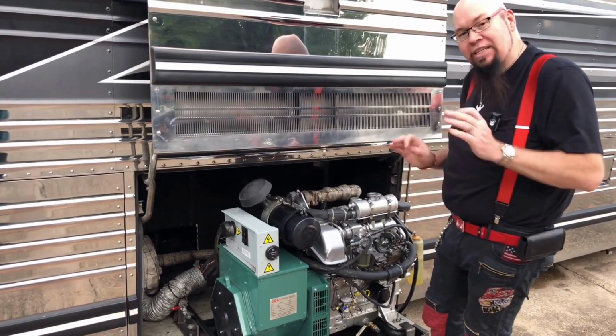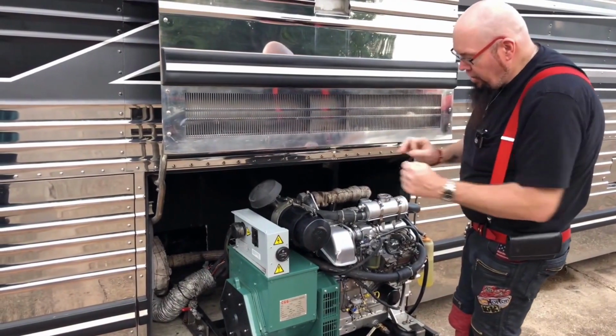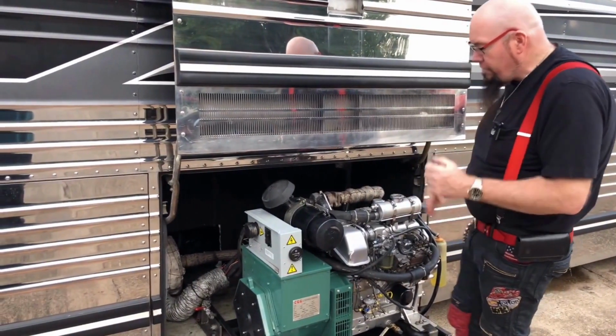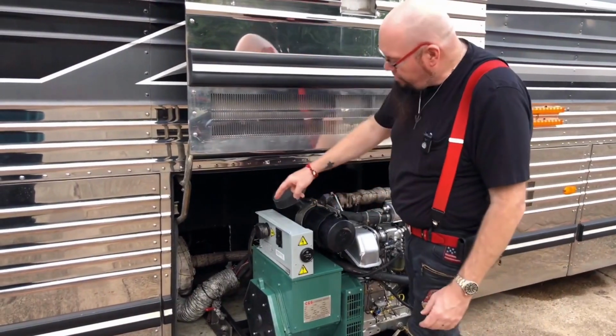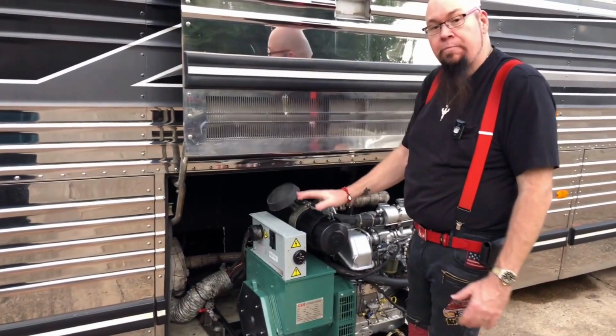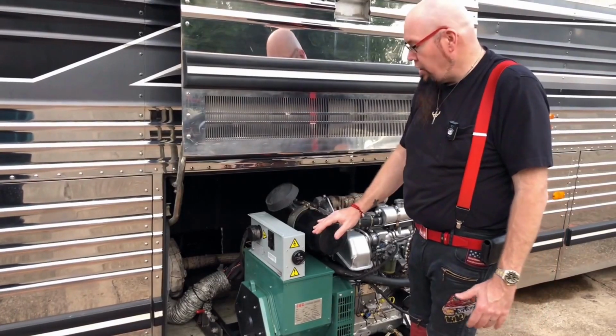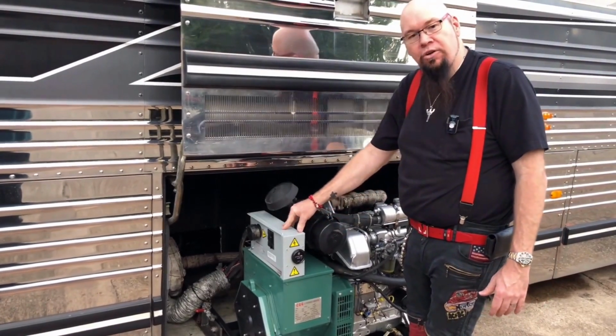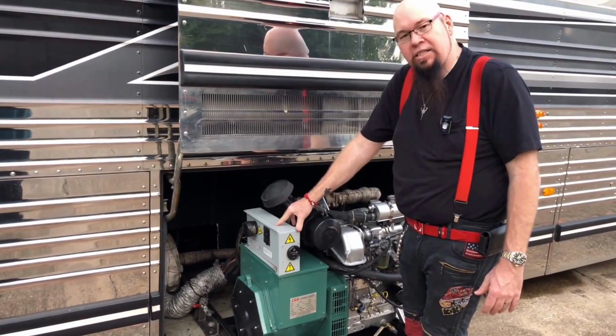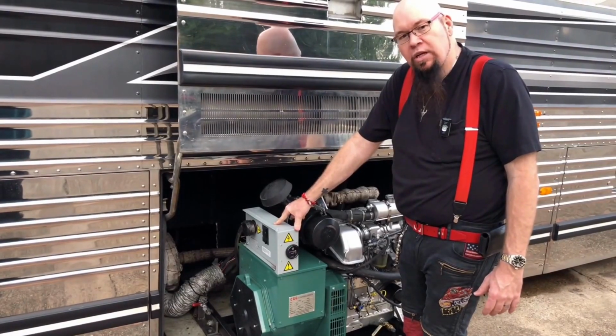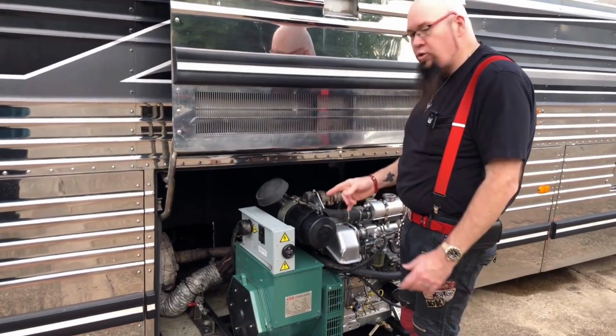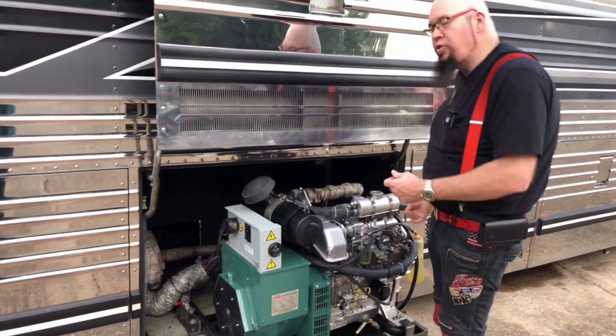You may have to adjust that slightly to get exactly the output you want. How you do that is by hooking up a quality meter that gives you hertz. In the United States, you want 60 hertz. As long as you're getting exactly 60 hertz, which produces 120 volts, you know you have the correct RPM. So when you install this, turn the RPMs down on your motor just in case.